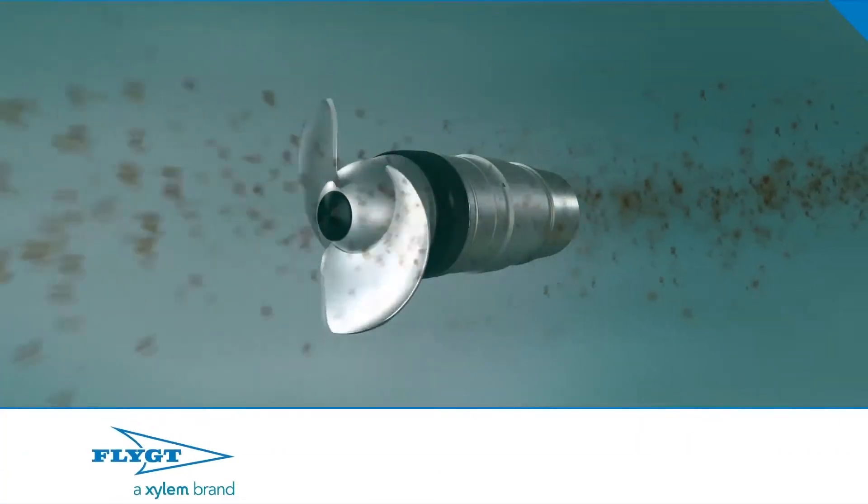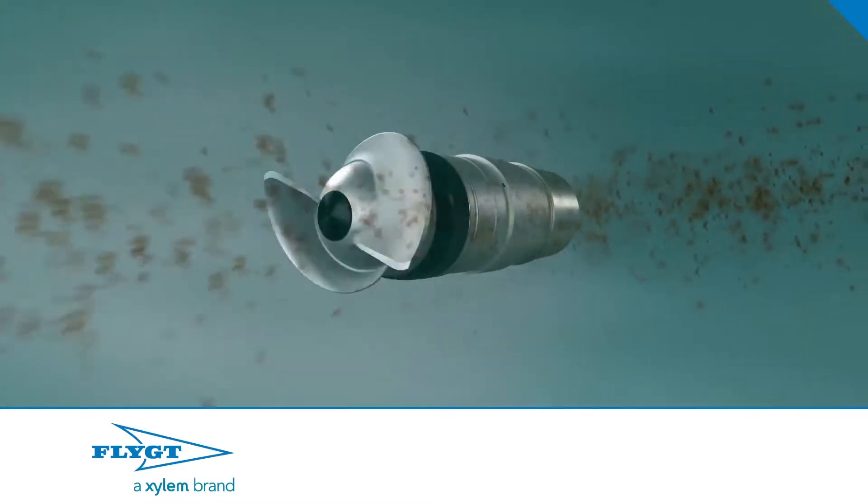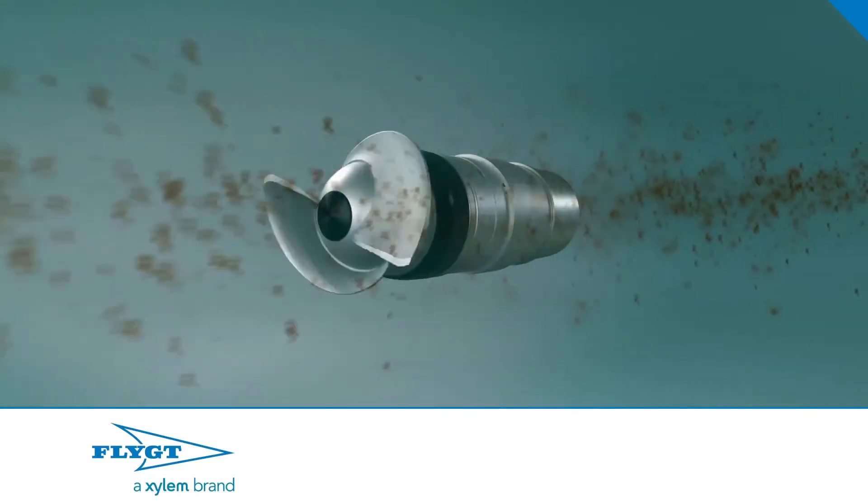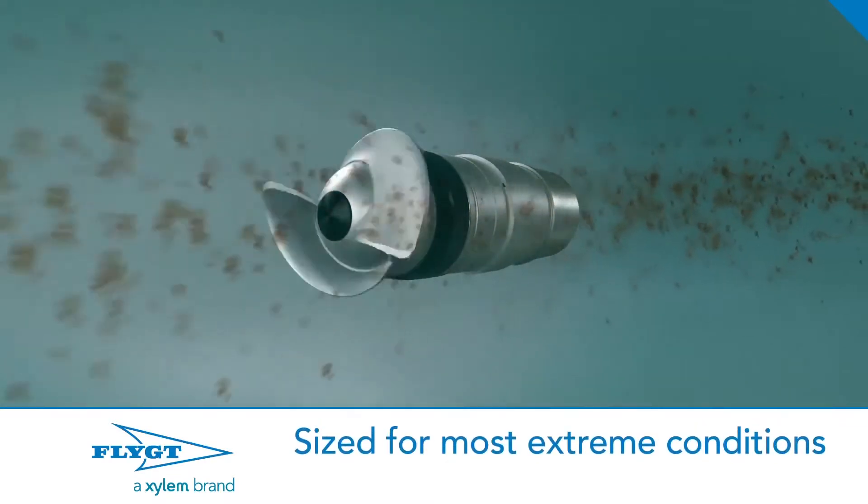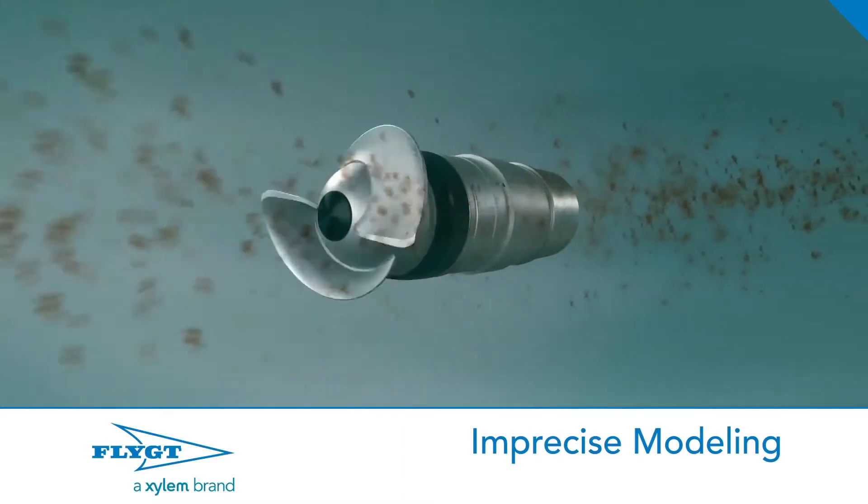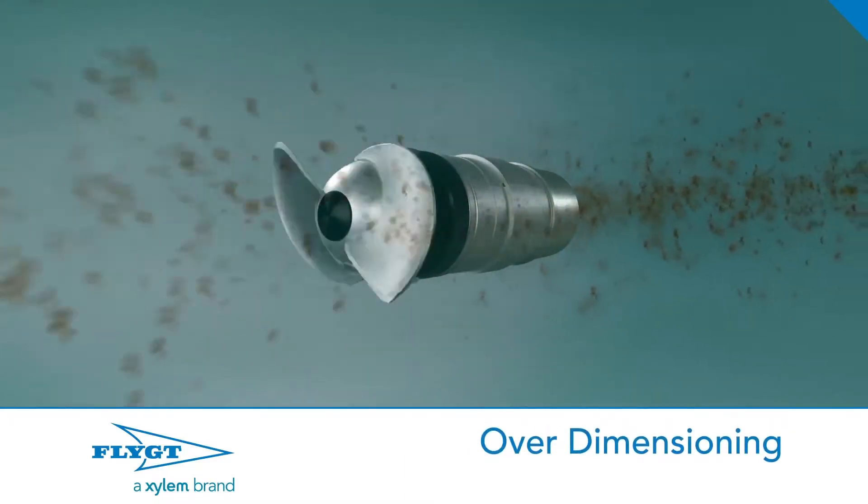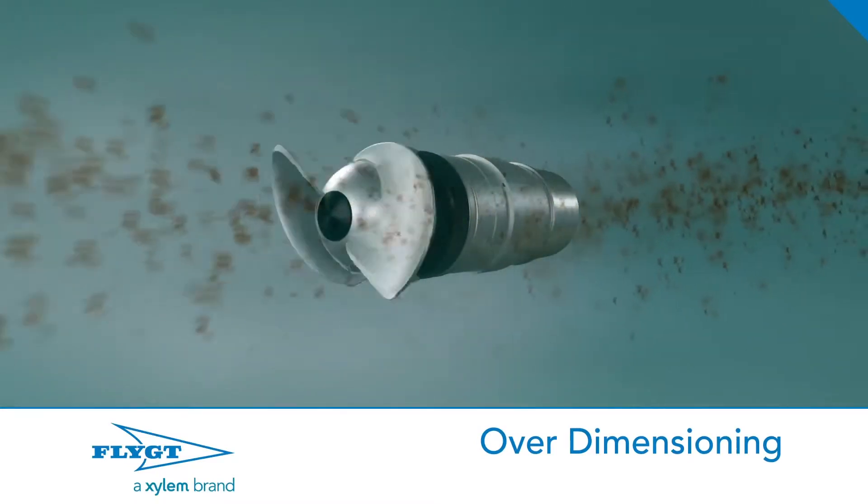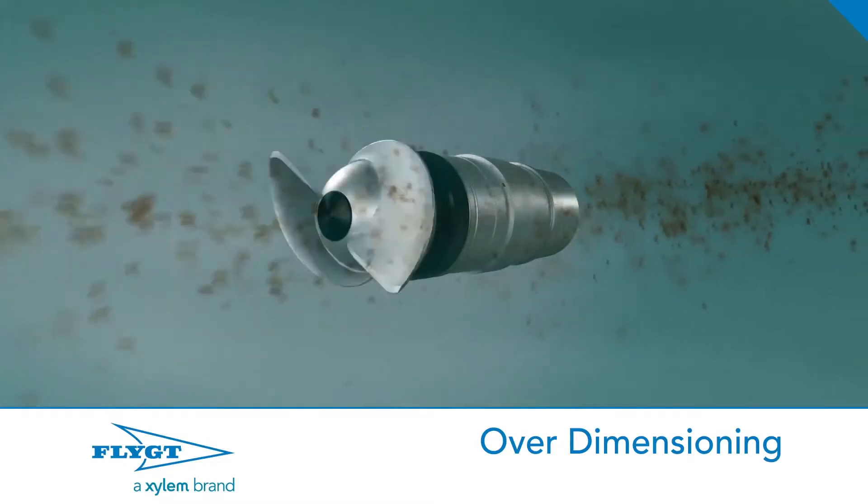Choosing the appropriate mixer is important. Today, however, most mixers are oversized for the job they are doing. This is usually because they are sized for the worst case scenarios, the manufacturers use older or imprecise sizing models due to the lack of experience in the application, or the mixers were sized without adequate consideration for issues like pre-screening, sedimentation, and location of inlets and outlets in the tank.